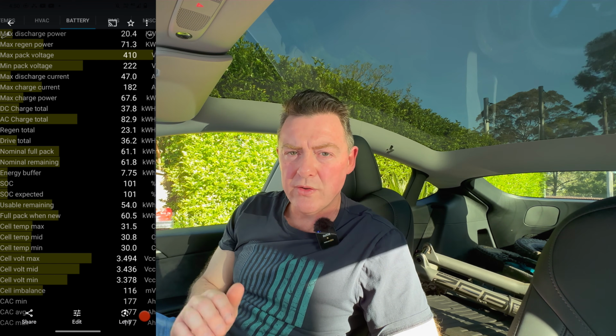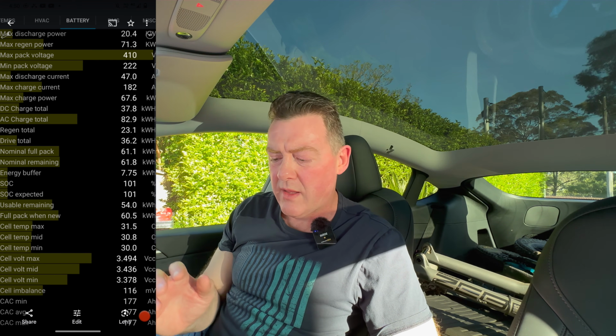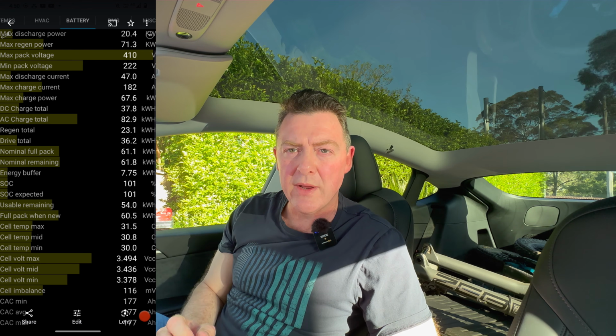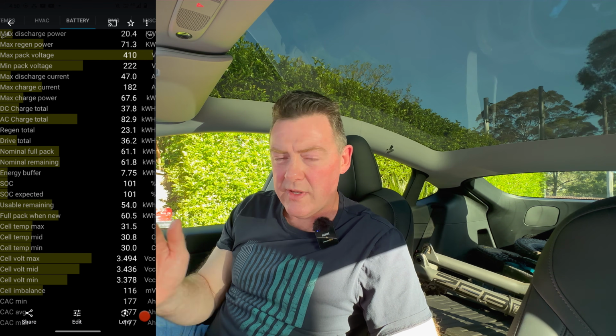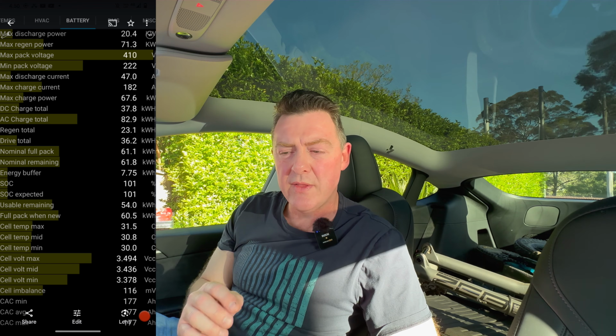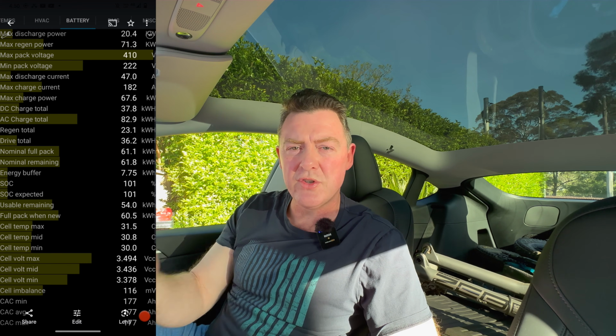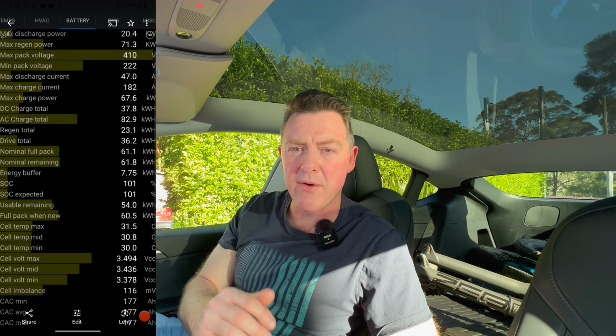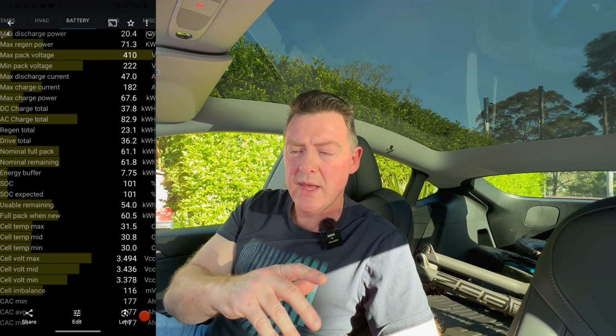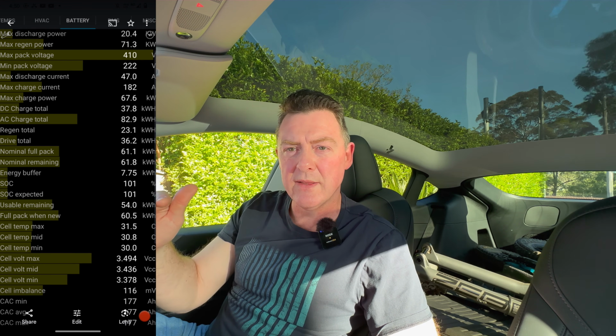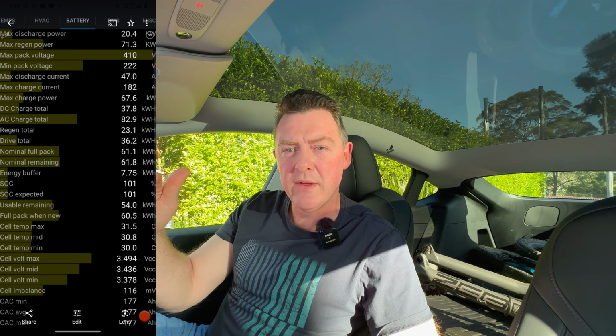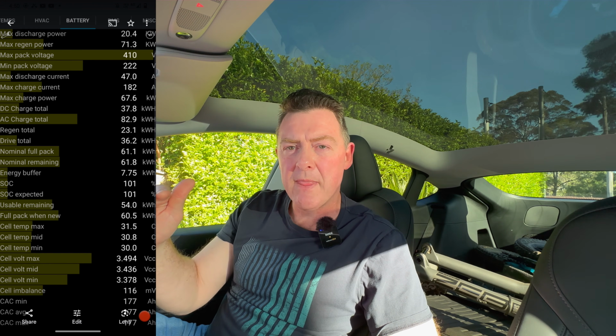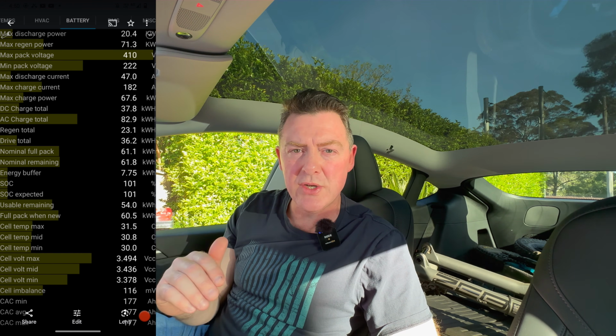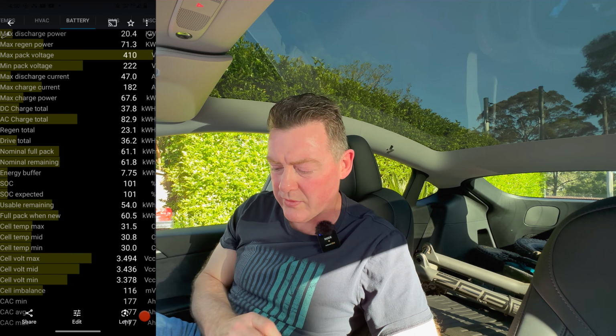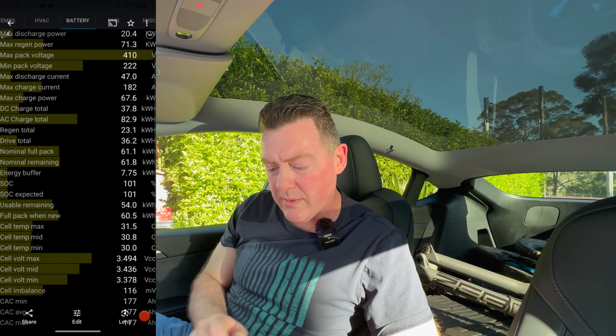So it's still trying to determine the energy that's stored in this battery. It's looking at discharging and charging, watching the energy discharged and recharged back into the battery, and comparing that against voltage, then charging up to full, getting the volts per cell to a 100% state of charge, and doing a bit of calibration each time it does a charge cycle. So it's actually pretty slow at doing that initially.